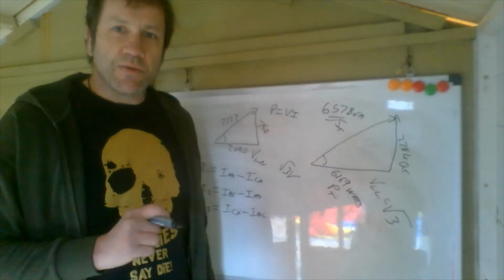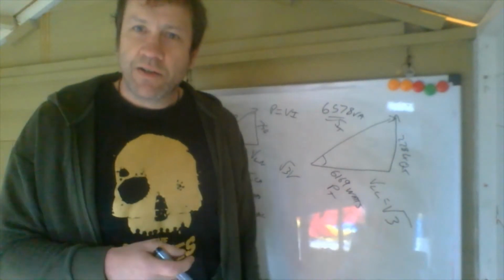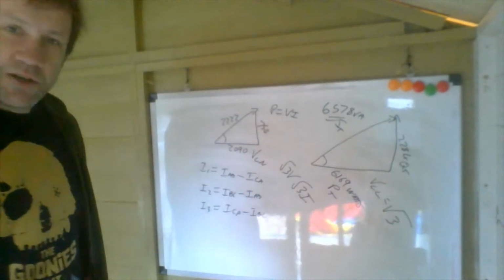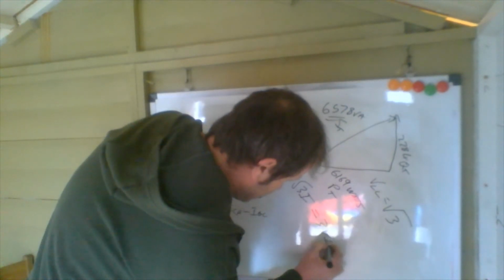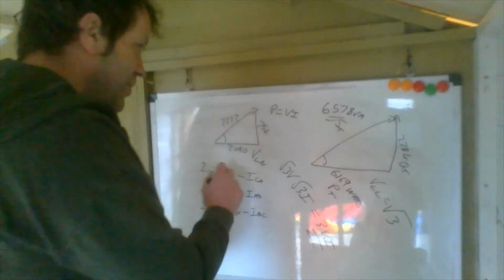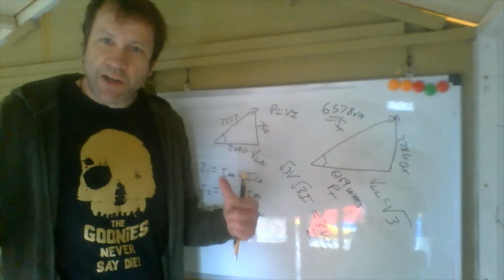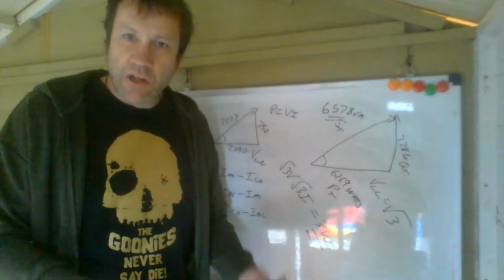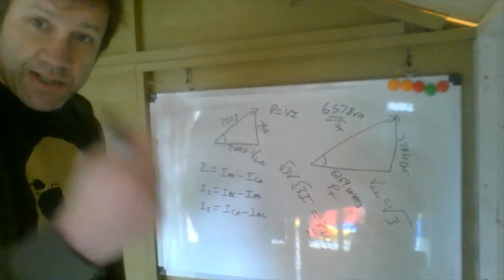But what's that going to do? That's going to draw the same proportion of current in. So you're going to get root 3 times the current. So what does that give you? That equals 3 times VI. In other words, because you're using line to line current, even though it's the same impedance as you're drawing in, you've got a root 3 times bigger voltage, which means you're going to have a root 3 times bigger current, which means you're going to have 3 times the power.